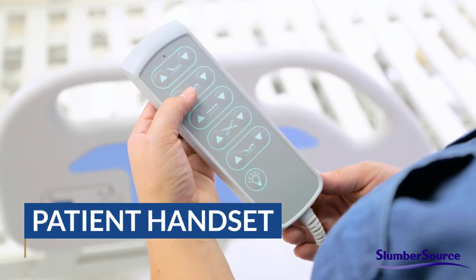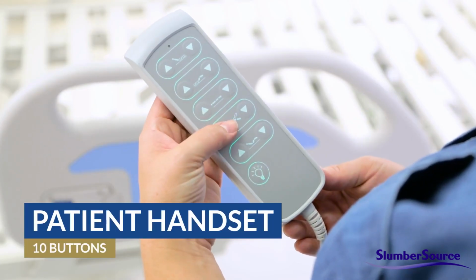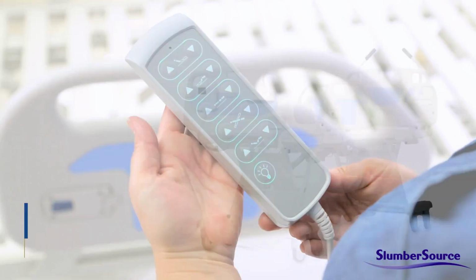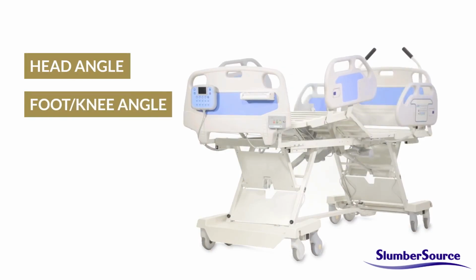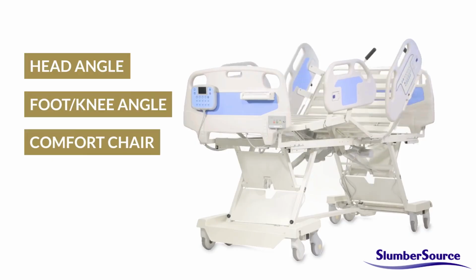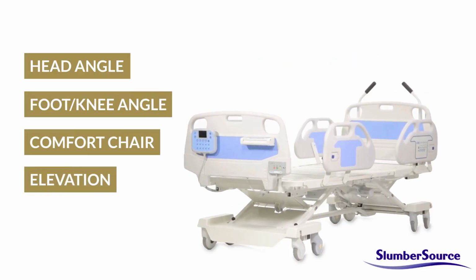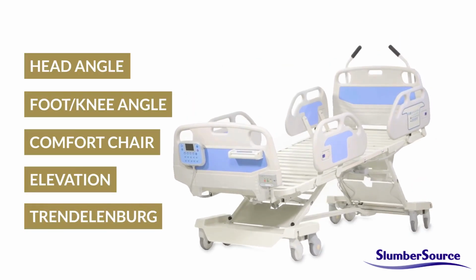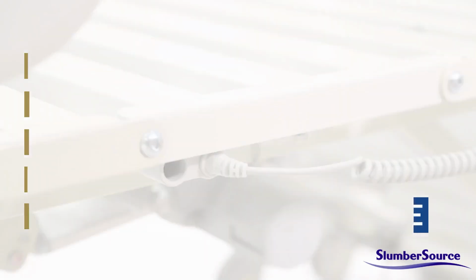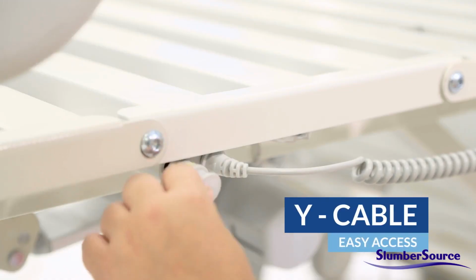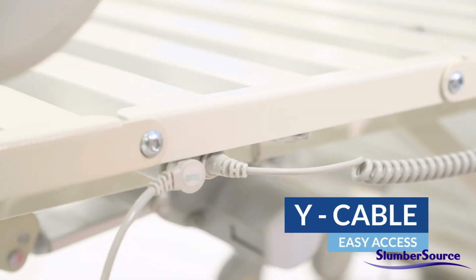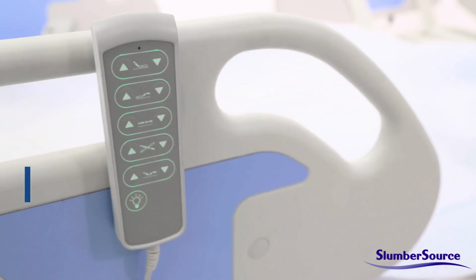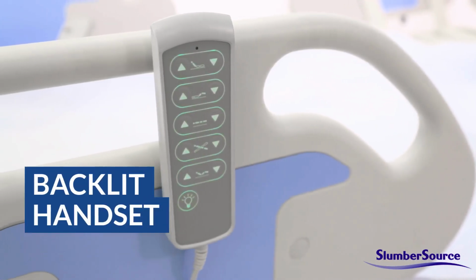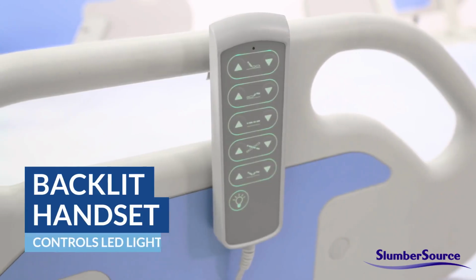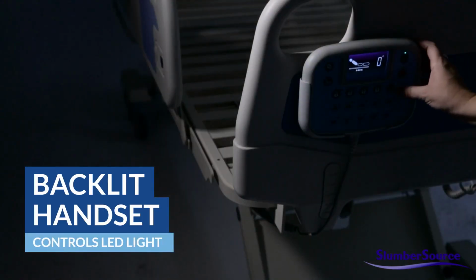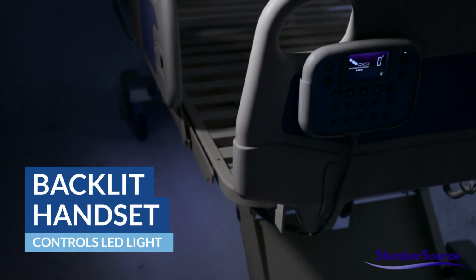The patient handset has 10 buttons which operate all bed functions. It has non-locking control of head angle, foot and knee angle, comfort chair, elevation, and Trendelenburg positions. A Y cable allows the handset to be plugged into either side of the bed to allow for easy and convenient access. The handset is backlit to provide ease of use for the patient or staff at night, and also controls an LED light under each side of the bed to reduce falls and assist with patient care in a dark room.